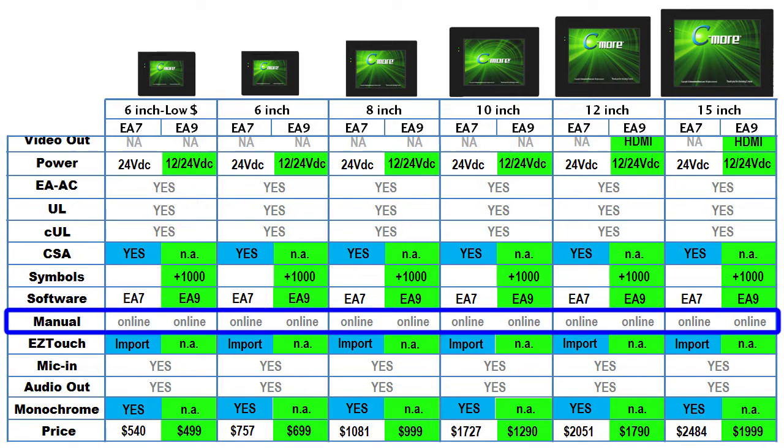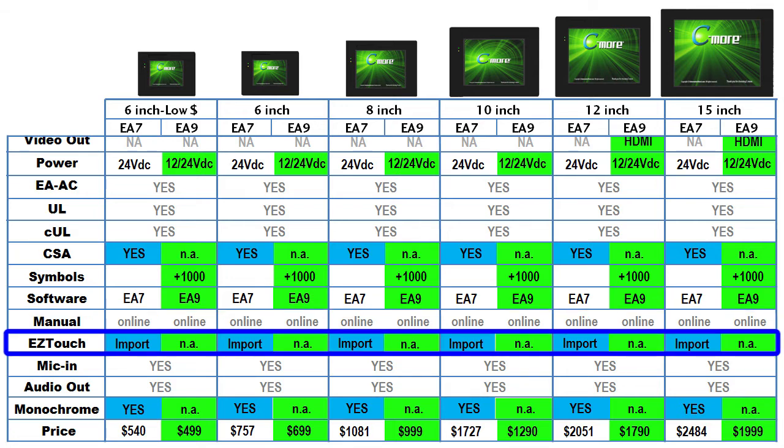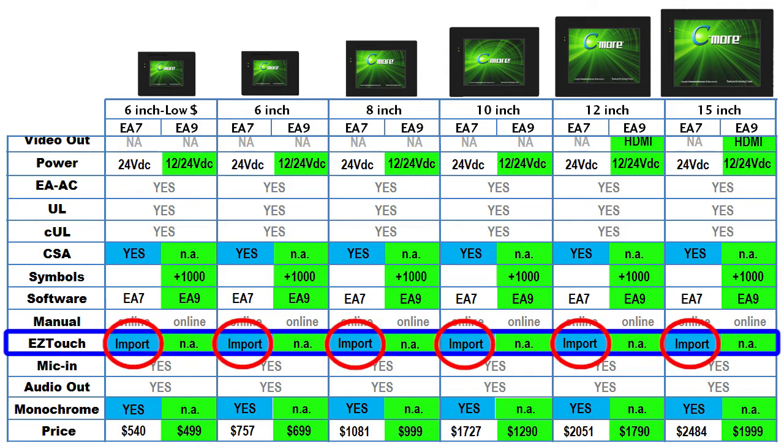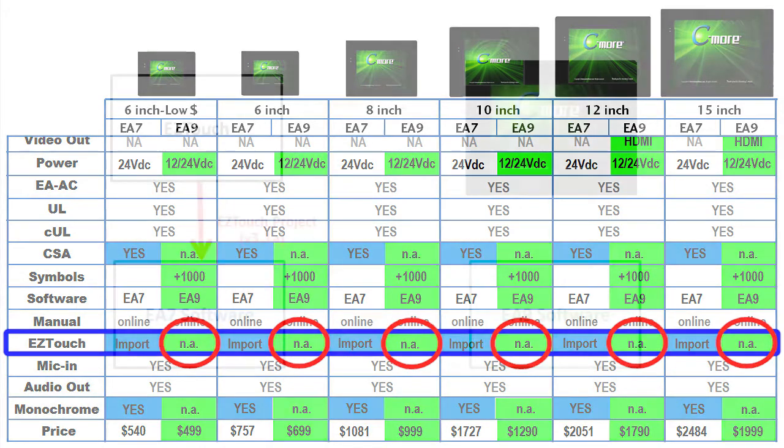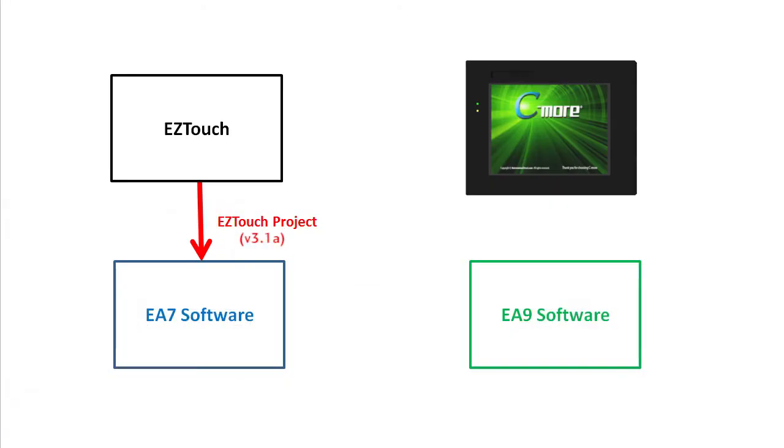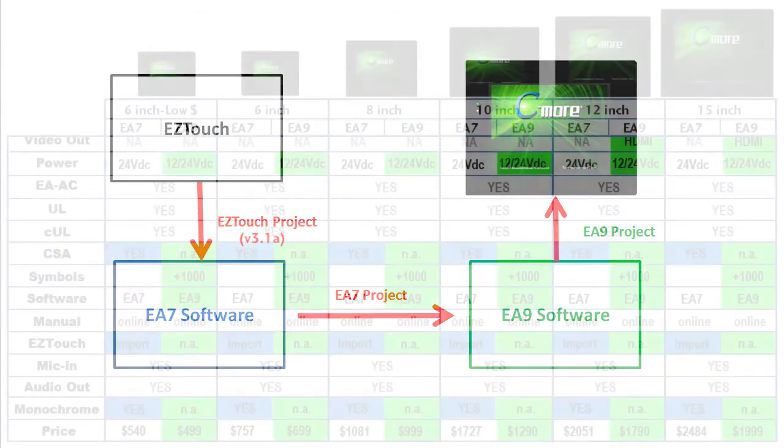Both user manuals are available for download at the AutomationDirect.com website. You can go download those right now. The original EA7 series has the ability to import EZTouch panel projects for panels that were purchased from AutomationDirect using the EZTouch edit software version 3.1a. The EA9 doesn't need to support that because it can read EA7 projects. Just bring the EZTouch project into the EA7 software and save it as an EA7 project. Then open the EA7 project in the EA9 software and you are good to go.